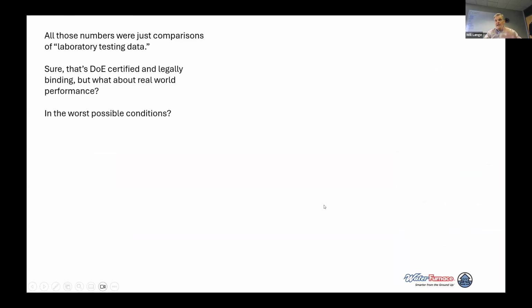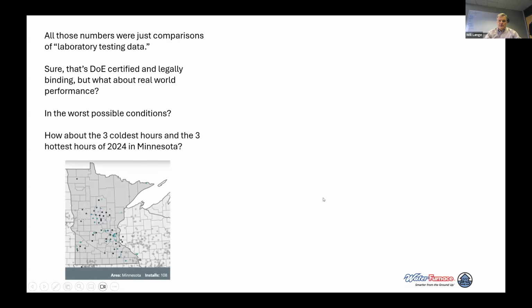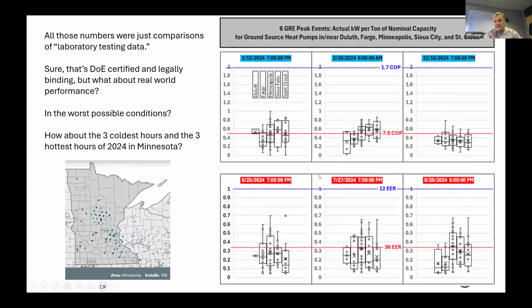But those are just laboratory testing data numbers, right? Who cares, right? Everybody can talk about your MPG may vary. So let's take a look at Minnesota, the 3 coldest hours of the last year in Minnesota and the 3 hottest hours. So these are extreme temperature performance ratings, actual observed temperatures. You see in the top left box, Duluth, Fargo, Minneapolis, Sioux Falls, and St. Cloud. And inside those dot plots, you can see where they came out in terms of kilowatts required per nominal ton of capacity. And the way that comes out is 360 readings over the course of an hour, every 10 seconds. So it's actual kilowatts measured of every component in the system, totaled up and plotted against nominal capacity.